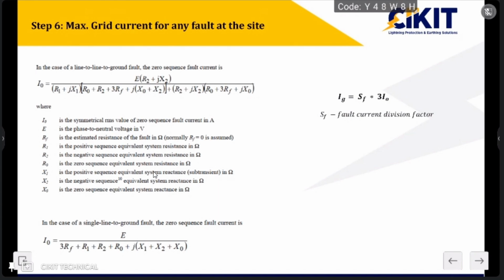But in most cases, the customer will have this fault level for the particular substation, and we can skip this step if we have the fault level, like 40 kA for 1 second or 25 kA for 3 seconds. The customer itself will have this. So if they have it, then this particular portion of the formula can be skipped.